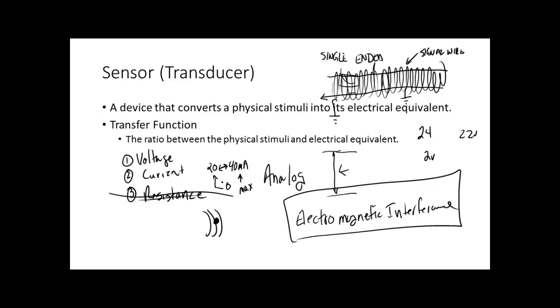And what's the advantage of current loop over voltage? Voltage is not necessarily more reliable. Normally signal leads are high impedance leads, which means if I'm using voltage and a high impedance source or channel, then it's going to be very easy to induce a voltage into the wire because it's dealing with an extremely high resistance. It's almost impossible for EMI to generate a current because it's a low resistance circuit, right?